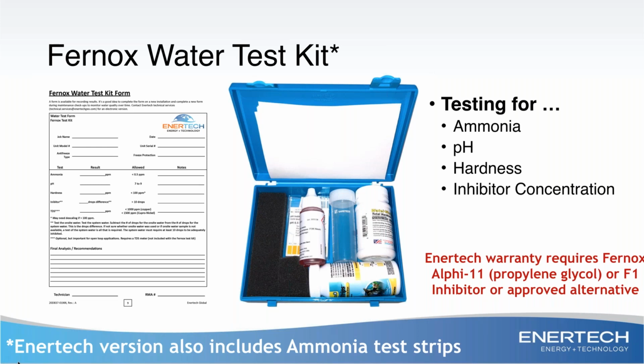So this is something that actually is part of our warranty requirements for both the Advantage unit and our geothermal heat pumps. We do require antifreeze on this product if it's going to be making chilled water. And it also requires the Fernox F1 inhibitors or an approved equivalent. So that is part of the warranty.